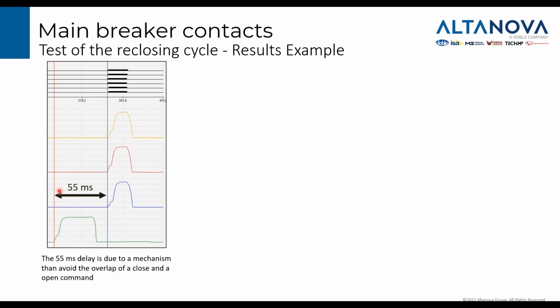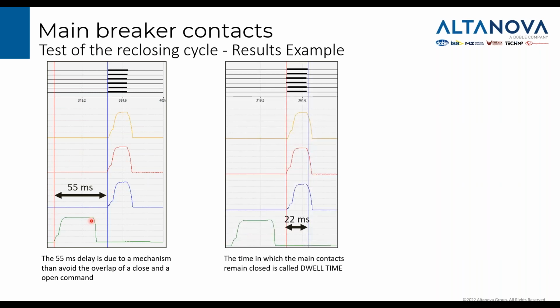It's important to test the time delay between the second close command and the second open command, because this delay should not be too much. This is also another important time that we have to test, because this is called dwell time or short circuit time. You can see that when you try to reclose on a fault, in this time the current will flow in the main contact. So this must be as short as possible.